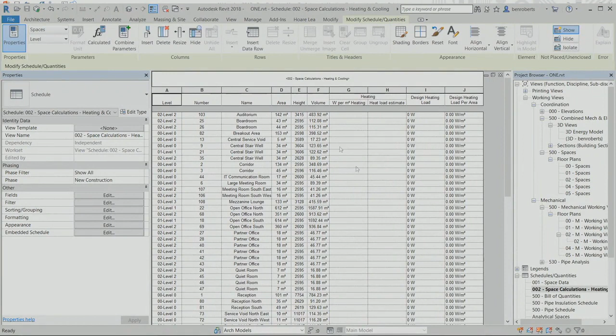And I've put in some checks just to say am I happy with these heat loads. Some of them I've put a conditional format, so some of them look a bit high, 95 watts a square meter, it's probably is a bit high. Might be something wrong, might need to look at it. Stairwell, it's probably just because it's got a really small floor area. So those are my heating loads, okay?